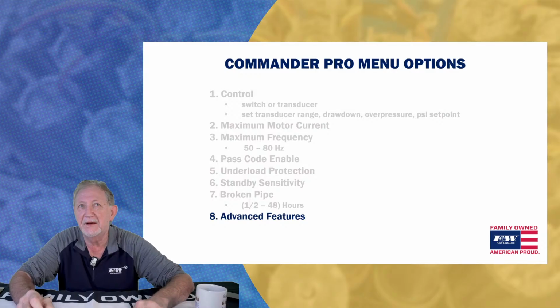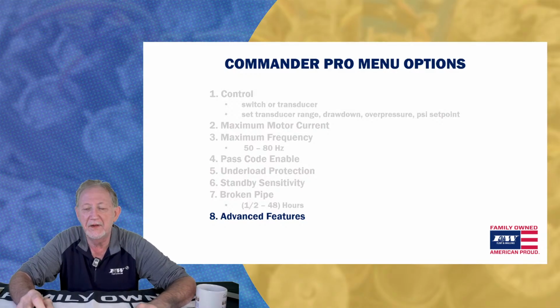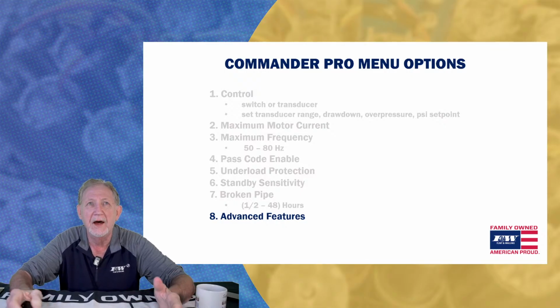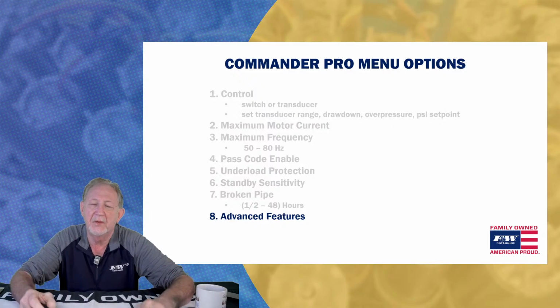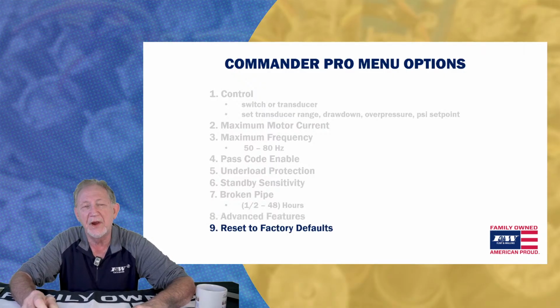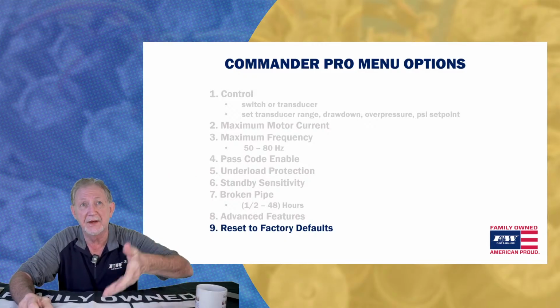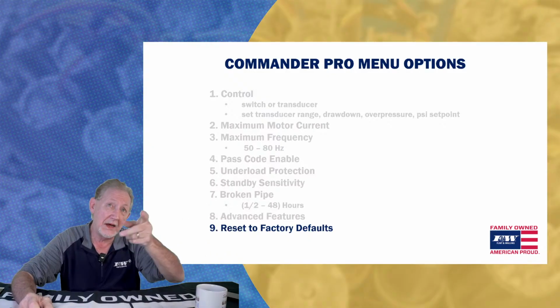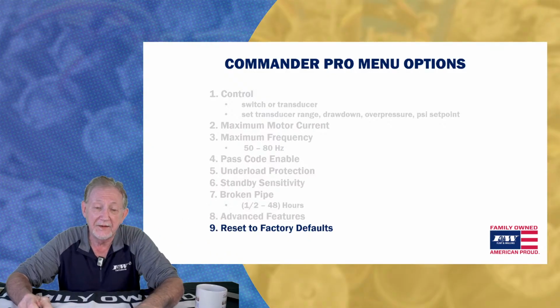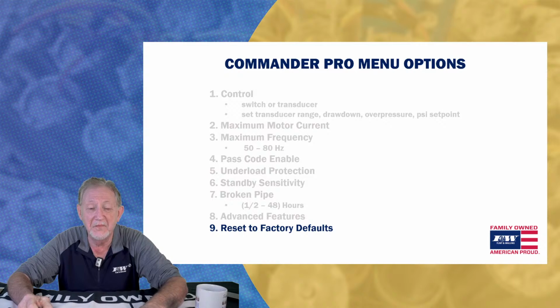That's where, not in there very often, but if you have remote alarms or float switches and things like that we want to operate, there's certain ways that we can wire those all into the drive and make all that work. Number 9 simply restores you back to the factory default. So you hit number 9, it's going to go all the way back. And by the way, you hit number 9, guess what? You're going to go through that quick start guide again.